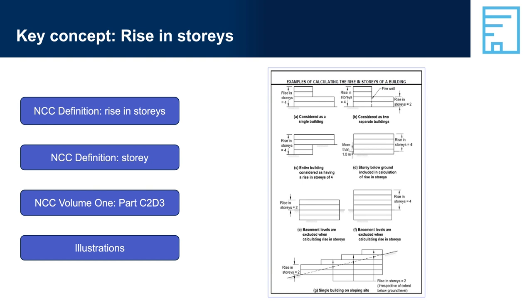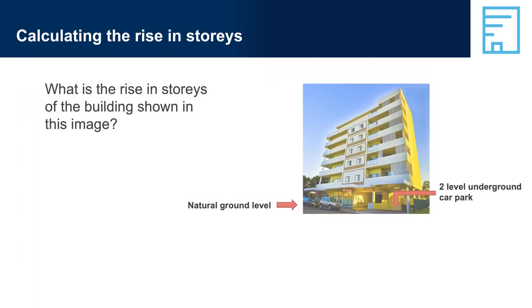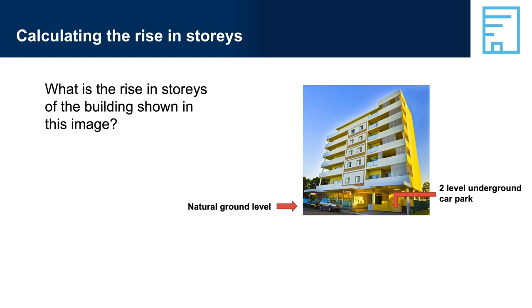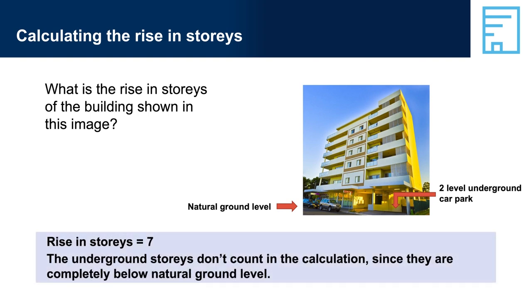The rise in stories of a building is used to determine the type of construction, along with the building's classification. Calculating the rise in stories: What is the rise in stories of the building shown in this image? The rise in stories equals seven. Underground stories don't count in the calculation since they are completely below natural ground level.